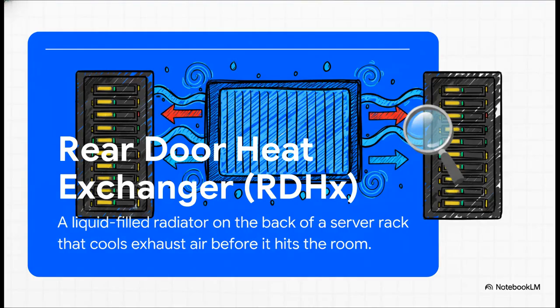Okay, so the first approach is kind of a hybrid. A rear door heat exchanger is basically a giant radiator that you bolt onto the back of a server rack. The server's own fans push all their hot air through this liquid-filled door, which cools the air down instantly before it ever gets a chance to heat up the rest of the room.